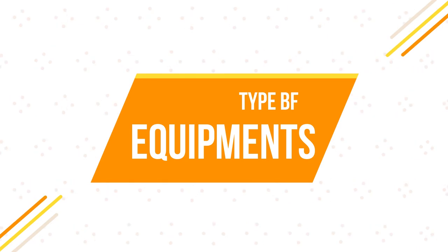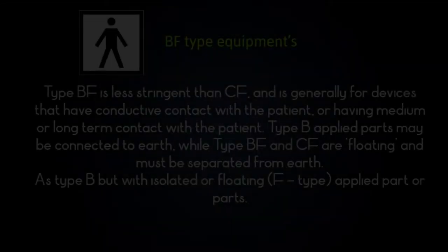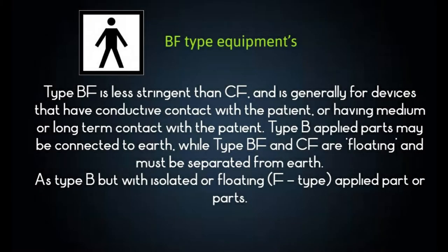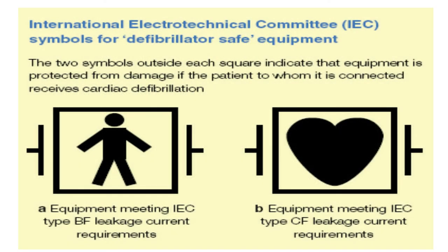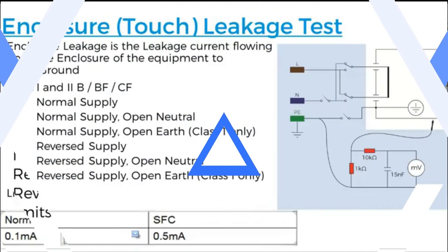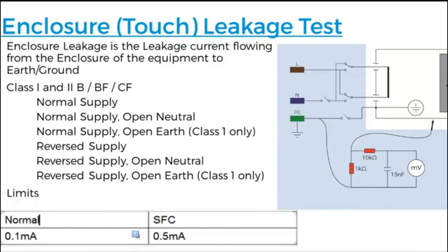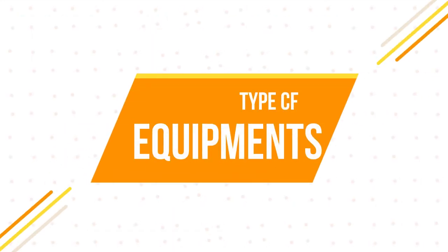The next type is BF Equipment. Type BF is less stringent than CF, and is generally for devices that have conductive contact with the patient, or having medium or long-term contact with the patient. Type B applied parts may be connected to earth, while Type BF and CF are floating and must be separated from earth, as Type B, but with isolated or floating F-type applied parts.